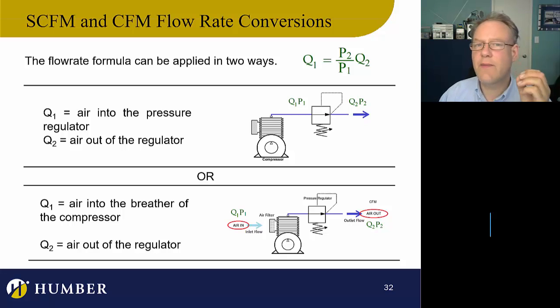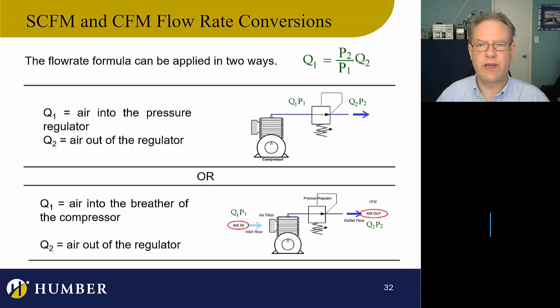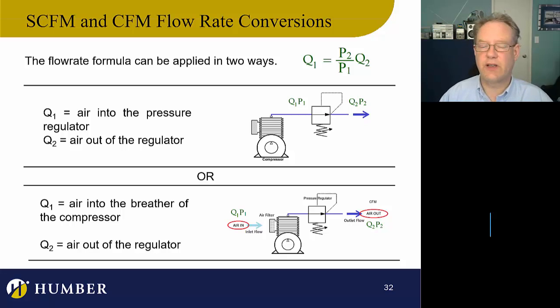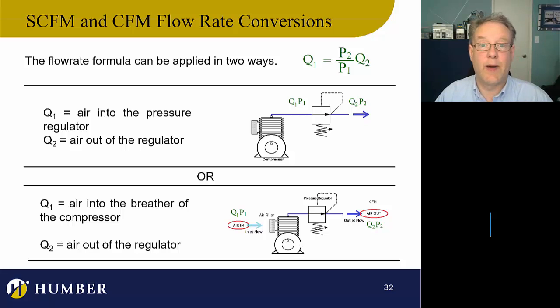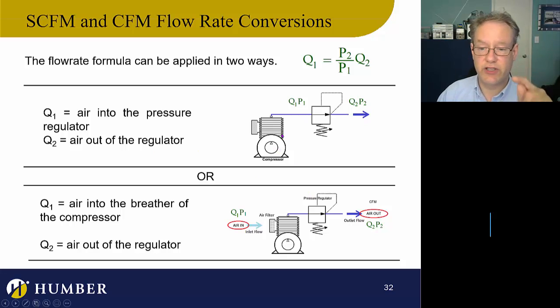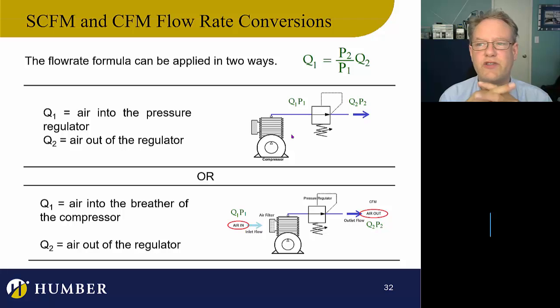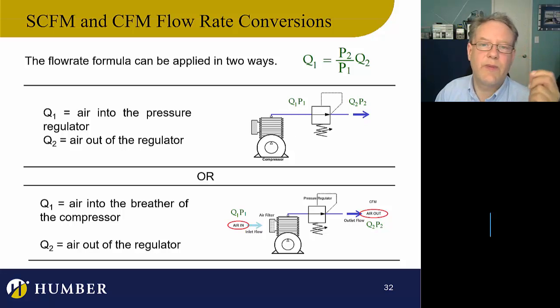The other way is that some compressors are rated for inlet flow rate — we don't discuss the inlet pressure because we know it's atmospheric, 14.7 PSIA. Sometimes that atmospheric pressure is lower, like on an airplane. But the same formula is used for both outlet-rated and inlet-rated compressors. For inlet flow, we use 14.7, or a lower number depending on altitude.